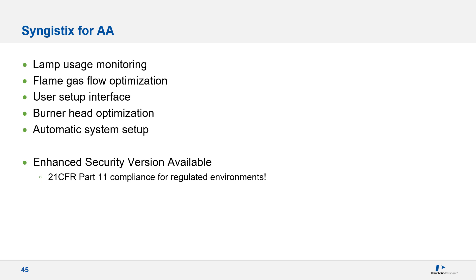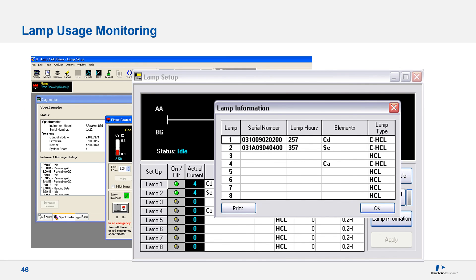Additional features provided with Syngistix software include lamp usage monitoring, gas flow and burner head optimizations, and rapid system setup through workspaces. There is now a programmable chip in each lamp that records total operating time, replacing the meter used on previous lamp designs. This allows a lamp to be easily used on multiple instruments since the information resides with the lamp itself. This information is highly beneficial as it allows a customer to evaluate long-term lamp performance by comparing time in use with the acquired energy number.